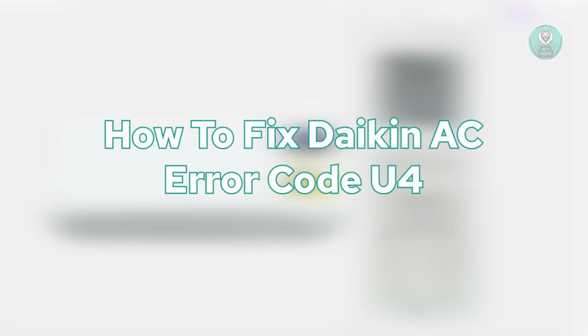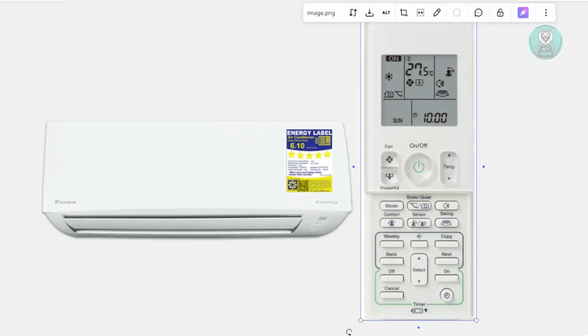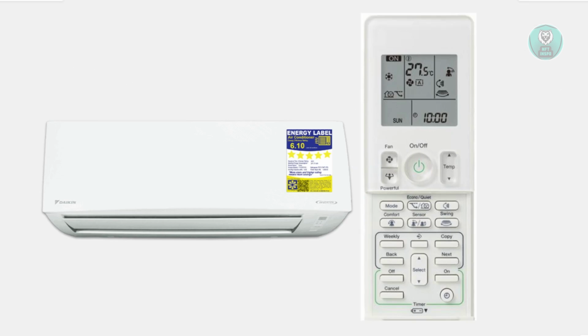For today's video, I'm going to show you how to fix Daikin AC error code U4. So if you're interested, let's get started. You might be wondering how exactly to fix your Daikin AC. Now if your Daikin AC is showing error code U4, it means there is a communication error between the indoor and outdoor unit. So in this case, what do you exactly need to do?